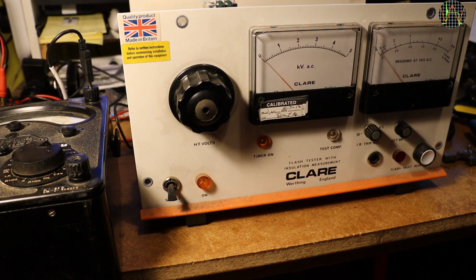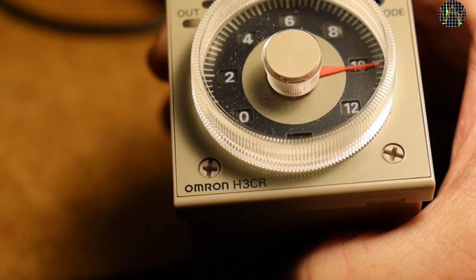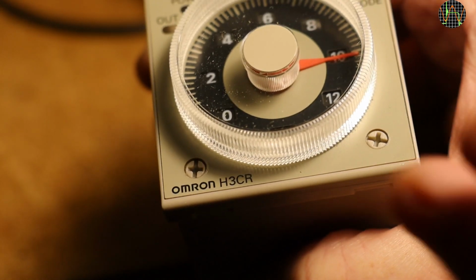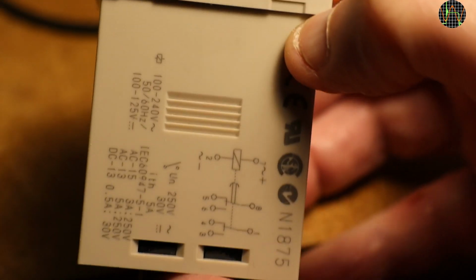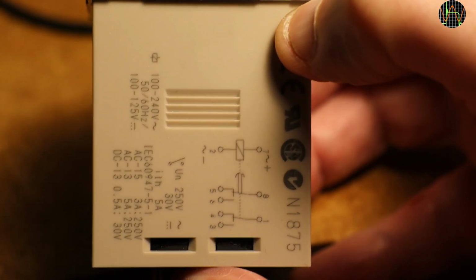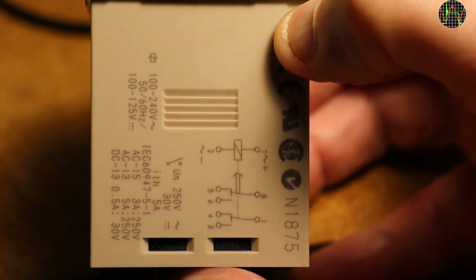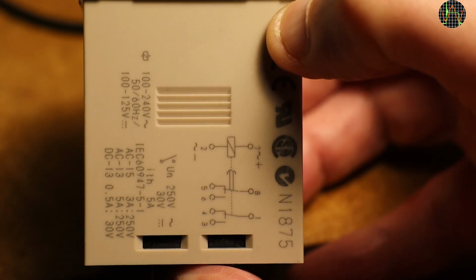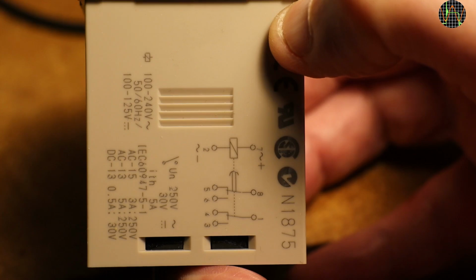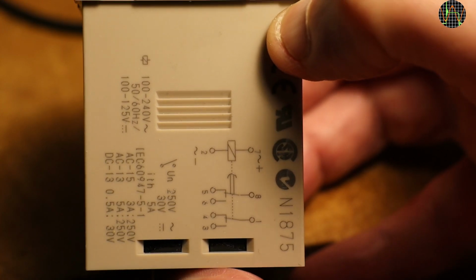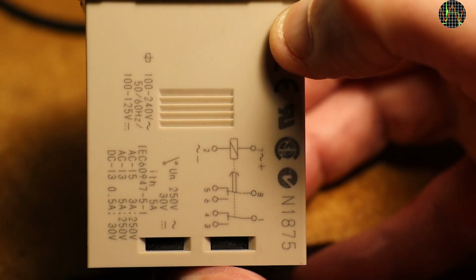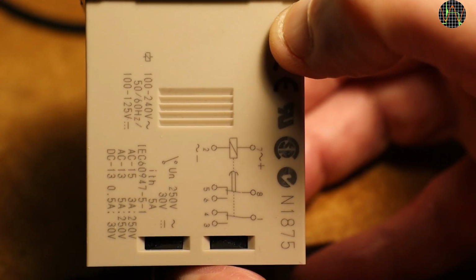I'm missing something here, but since I have no manual, the only way is to study the unit itself. Let's start with a timer, which can be easily unplugged from its socket. It's an Omron H3CR set to 10 seconds. Thankfully, Omron has printed the pin out on the unit. From what we see, 2 pins, 2 and 7, are needed to activate it. And there are 2 sets of contacts that are driven by the timer, but not the same way. Clearly the upper set is driven differently from the lower set.